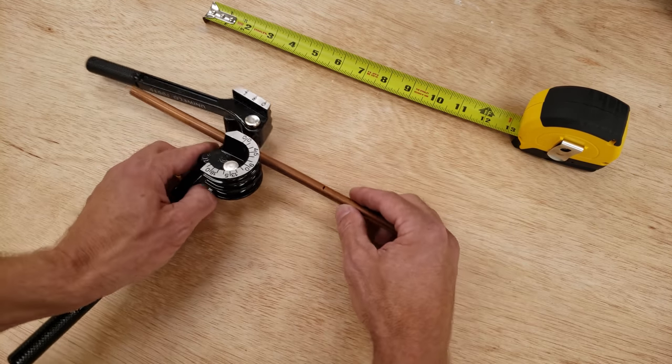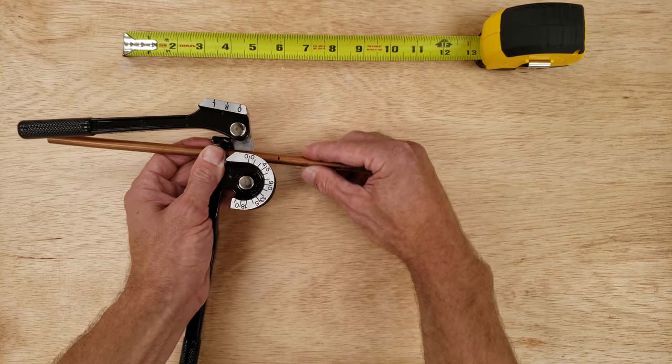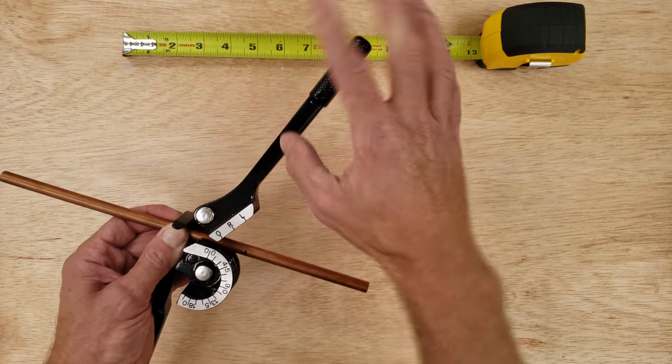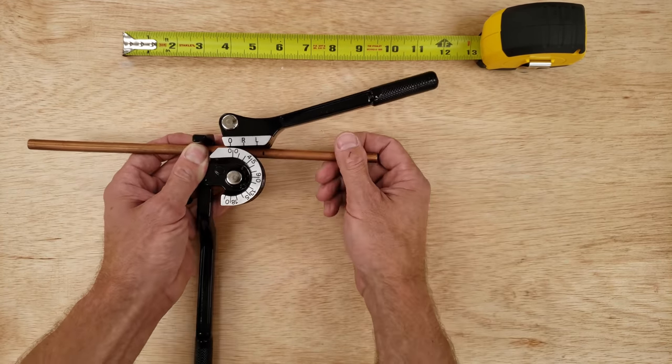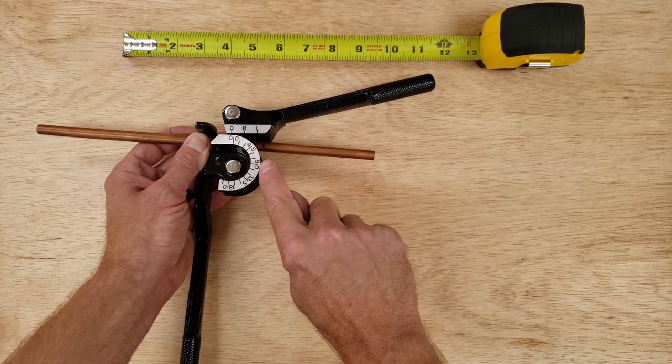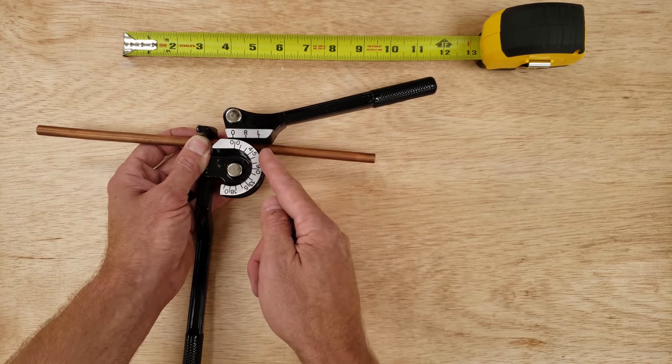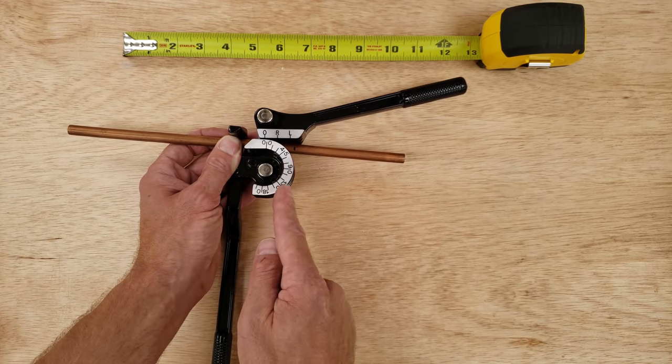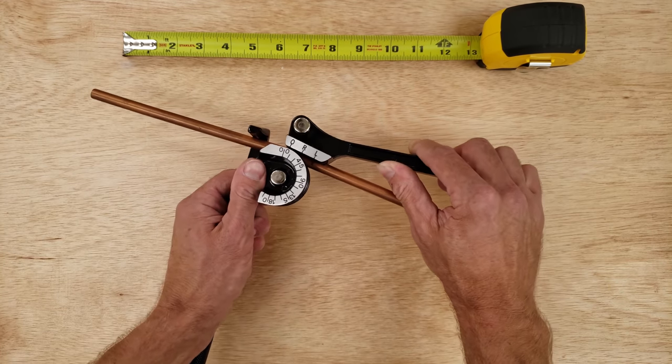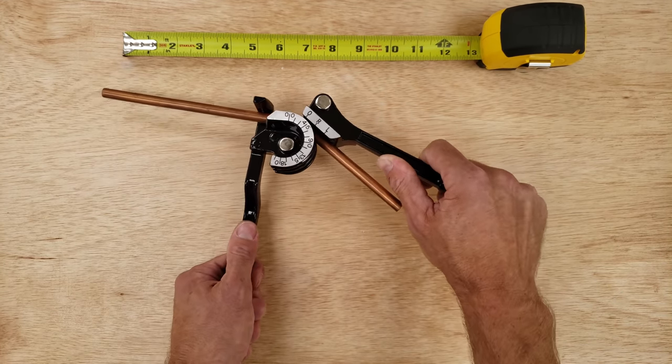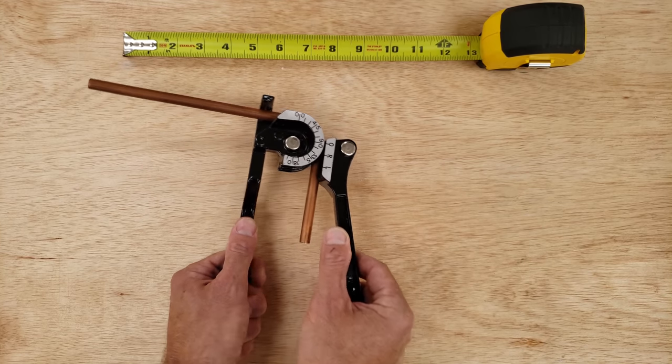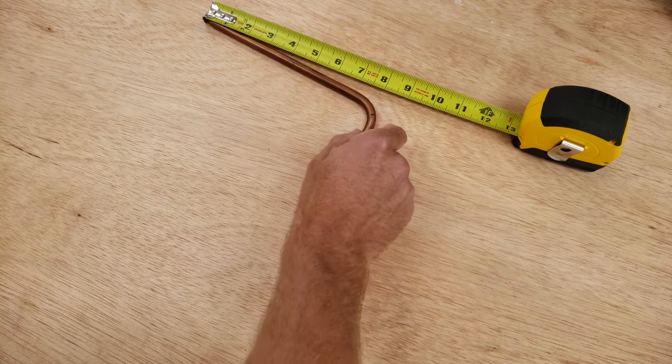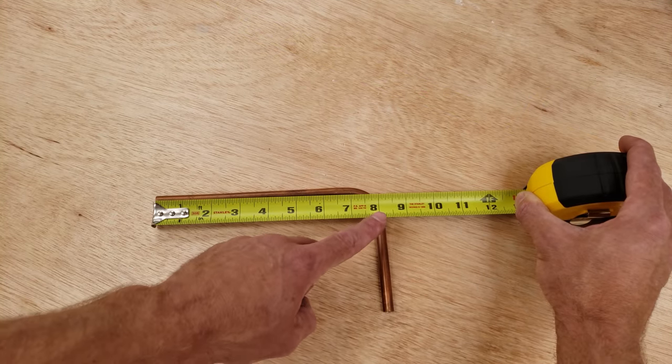We're going to slip it in here and make sure that this mark is right on the edge of this. We're going to fold this over and verify that mark is in line with the edge. When we're done, we're going to measure from here to the center of our 90 degree bend and it's going to be eight inches. So here we go, we're going to bend this right to 90 degrees. As you can see, that eight inches is right in the center.